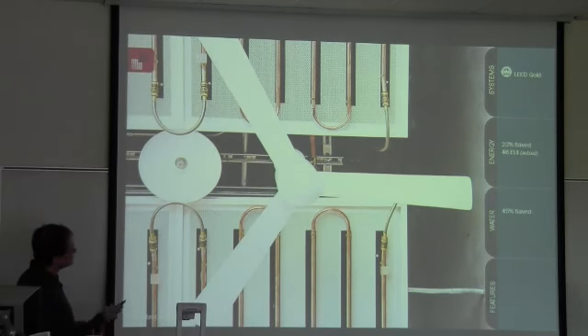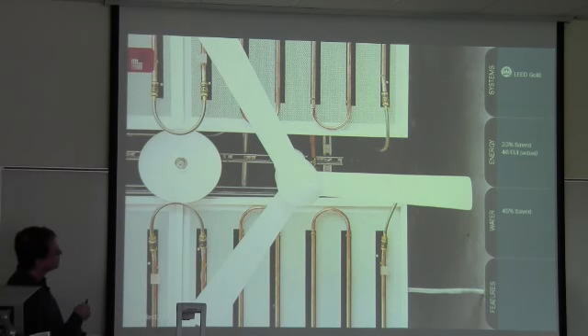But this design was a first generation of ceiling radiant panels that were 2-pipe changeover. So every one of these rails sits on the panel, and these are the pipes that contain the fluid, and the fluid's all controlled from either a control valve or a pump for every zone, and so it changes the panels from heating to cooling depending on what the space needs.